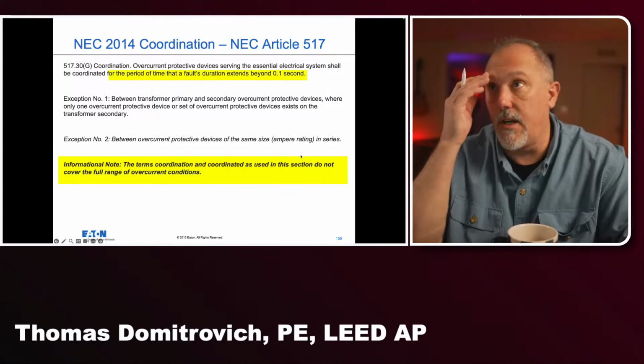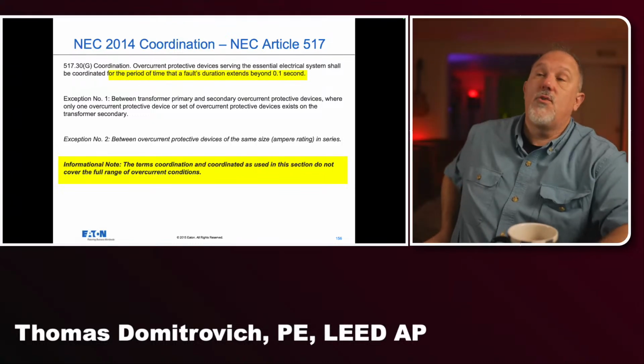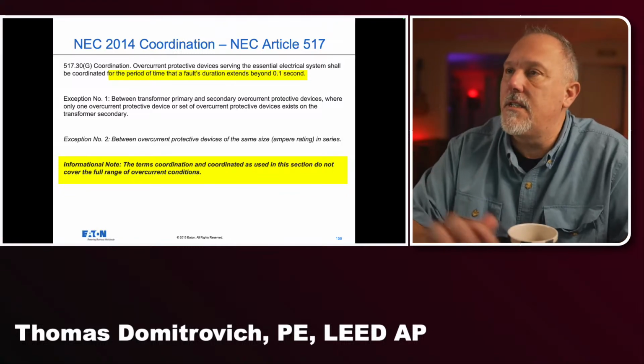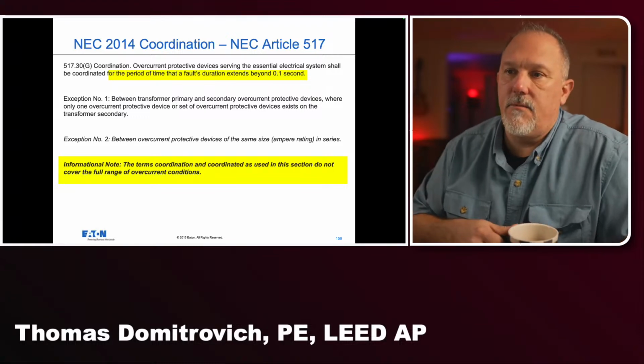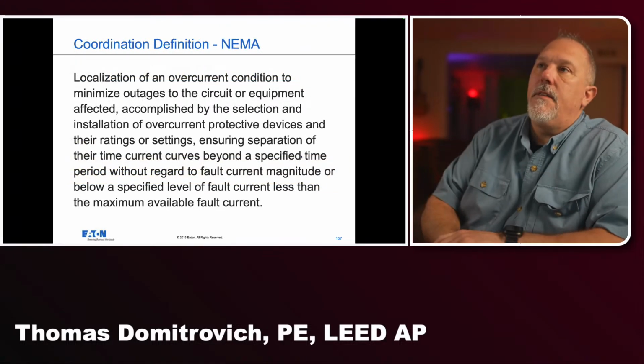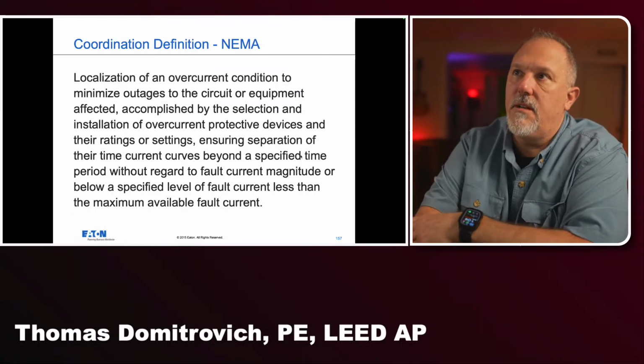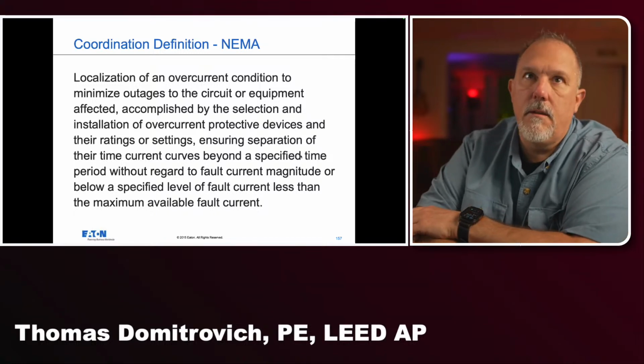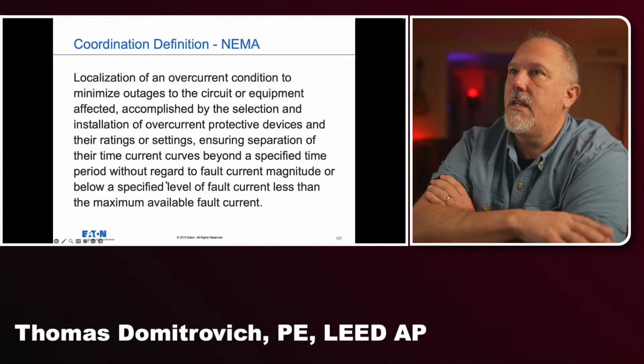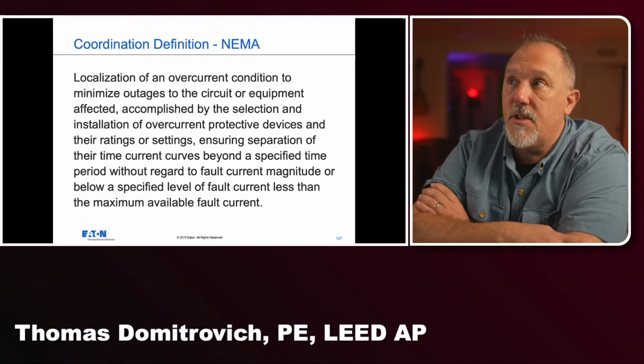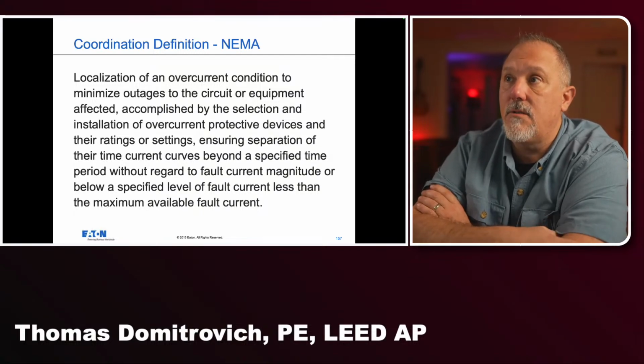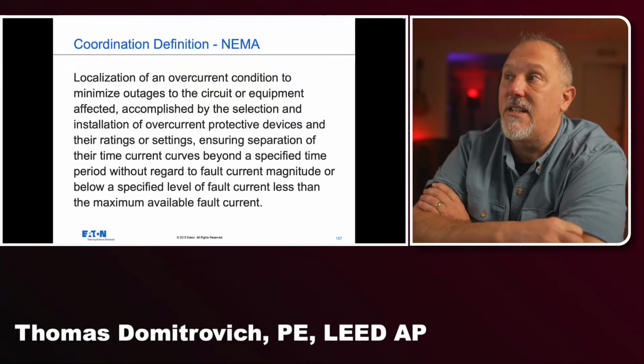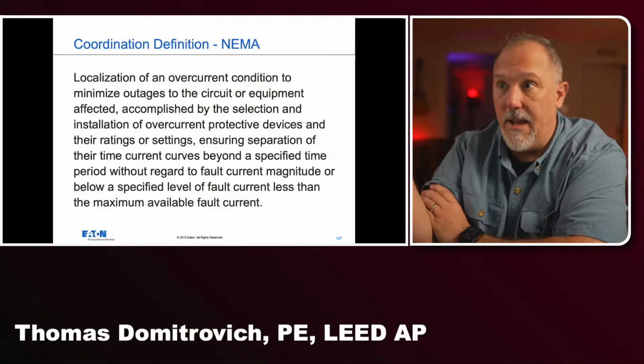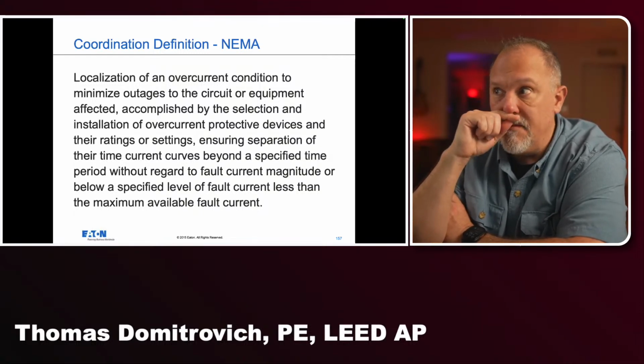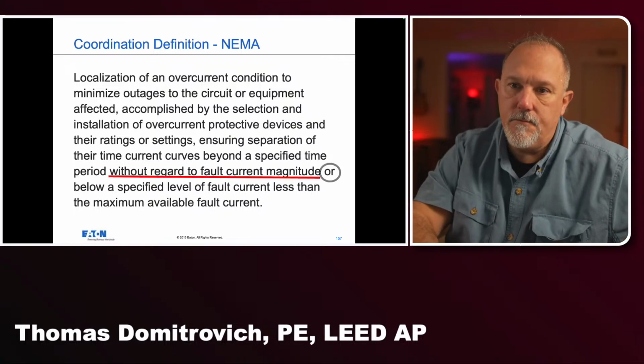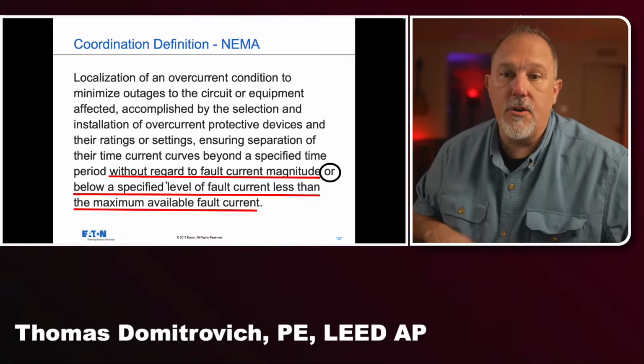Coordination is 0.1 seconds. So 517.30(G), this was the 2014. That's how old this presentation is. And I've been teaching this and making sure that people understand what this is. Now, NEMA came out with a document that said that coordination is localization of an overcurrent condition to minimize outages to the circuit or equipment affected, accomplished by the selection and installation of overcurrent protective devices and their ratings or settings, ensuring separation of their time current characteristic curves beyond a specified time period without regard to fault current magnitude, below a specified level of fault current less than our maximum available fault current. So without regard to fault current, or below.